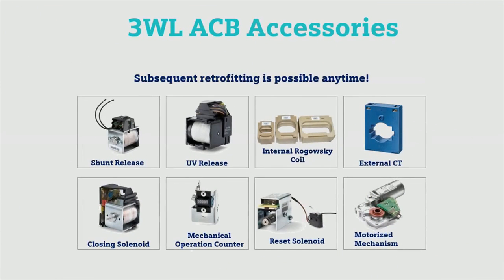These are the accessories that can be changed during maintenance: shunt release coil, undervoltage release coil, internal Rogowski coil for current sensing, external CT coil, closing solenoid, mechanical operation counter, reset solenoid, and motor mechanism for spring charging.